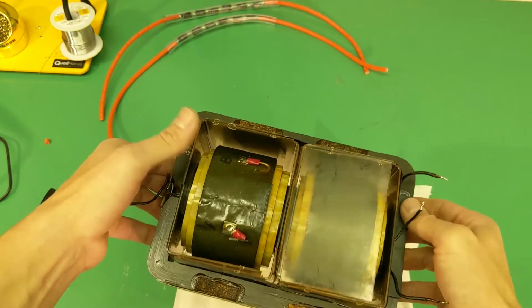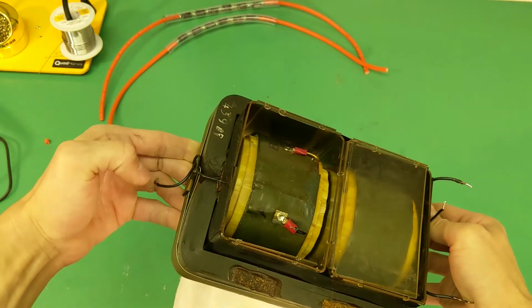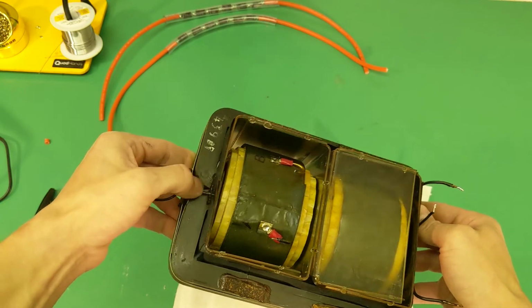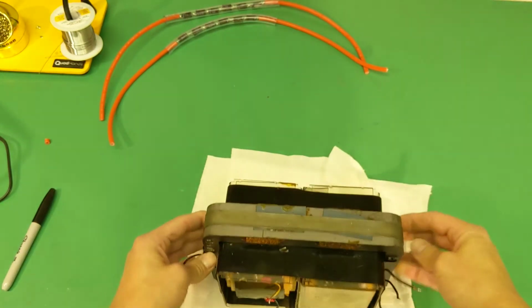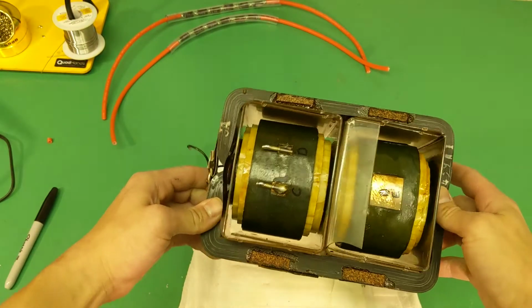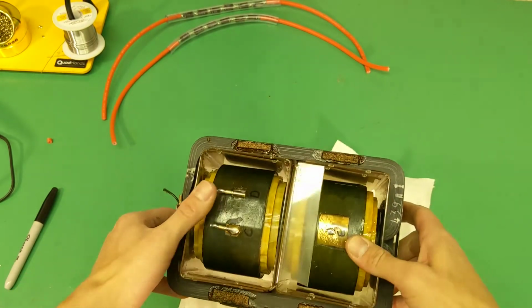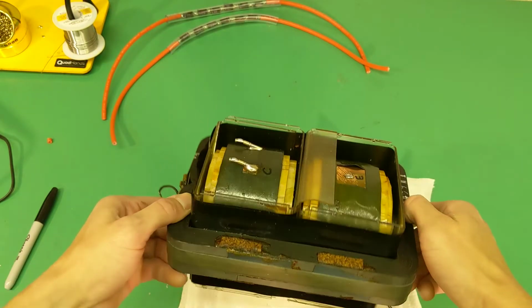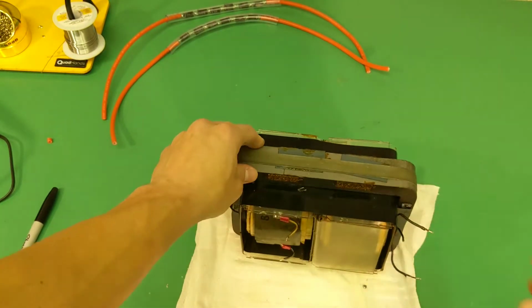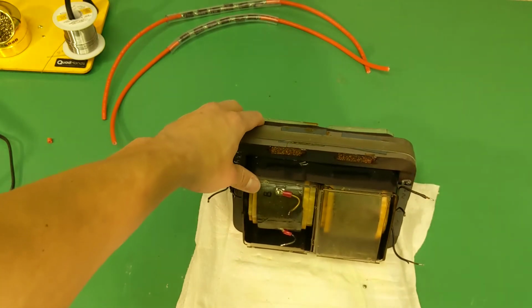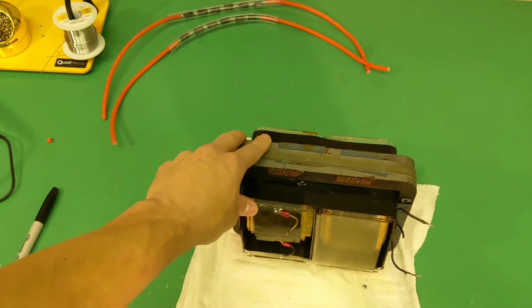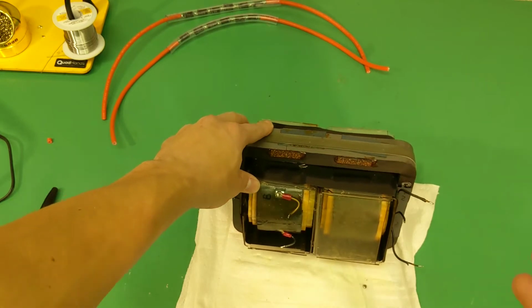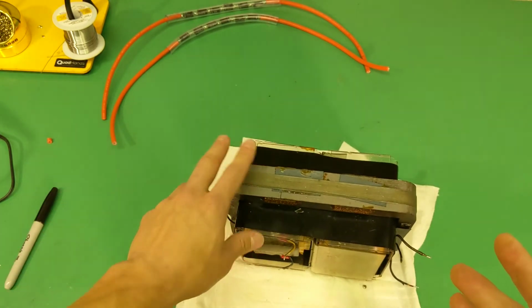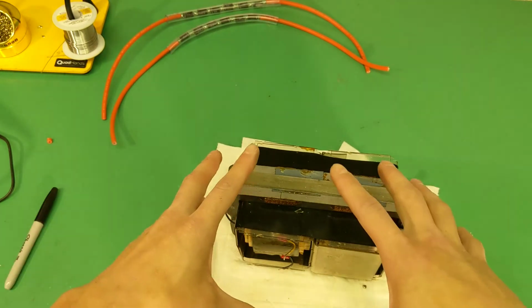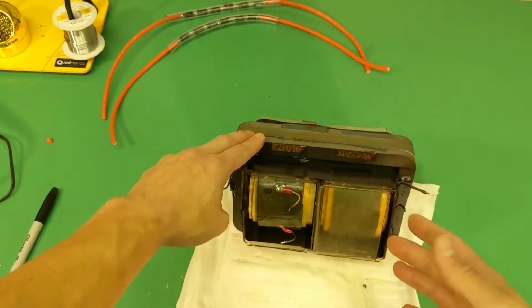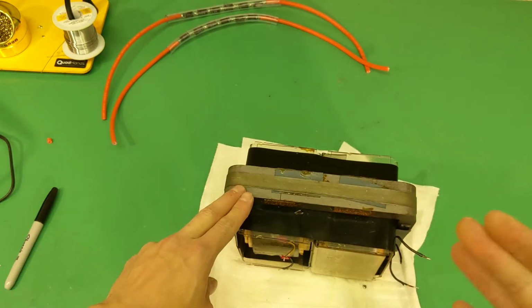There are 3 wires here, 2 wires here, a center tap wire going into the transformer, and on the other side 3 more connections - this one and these 2. Most designs should be simple to understand, and if you look online, X-ray transformers typically have 4 or 5 connections coming out. This one has 9. So how do you start with something with 9 connections going to places you really can't tell, and figure out how it's internally wired?